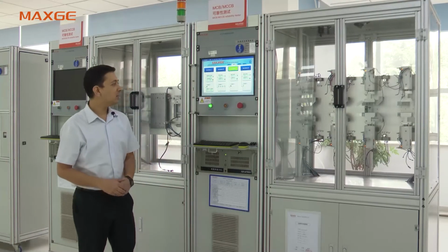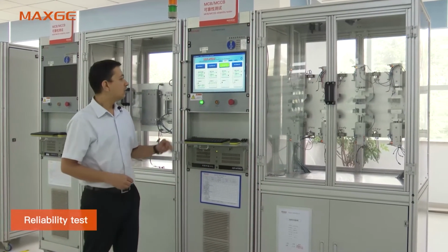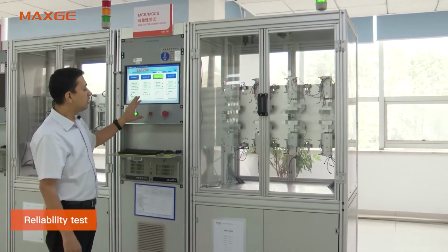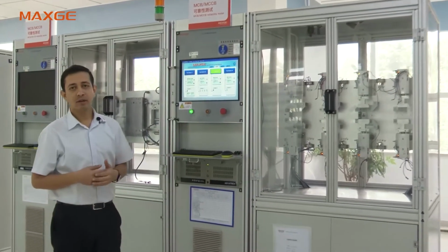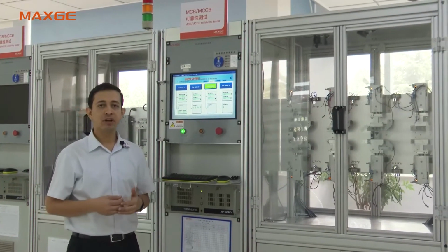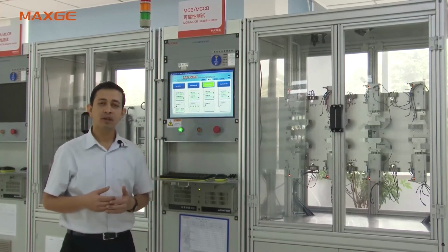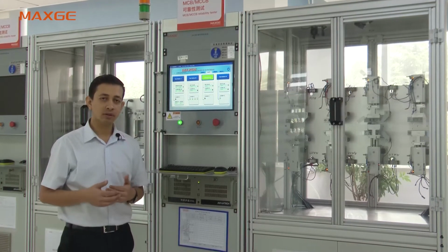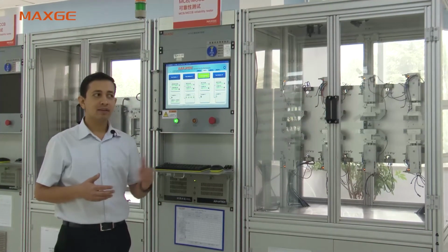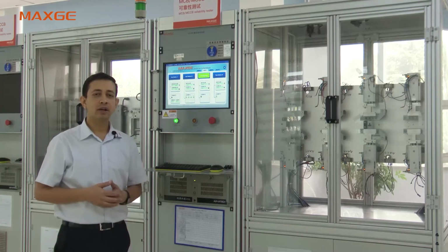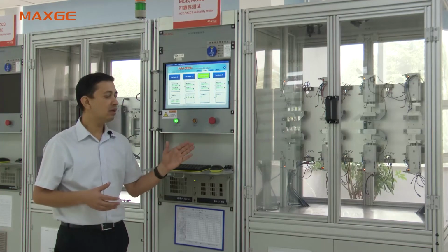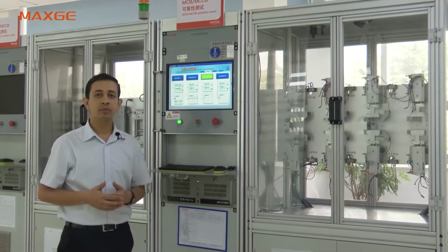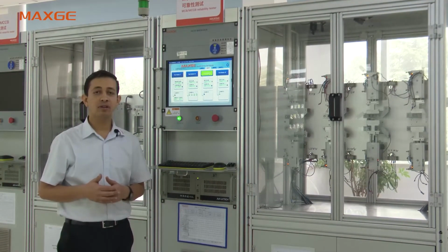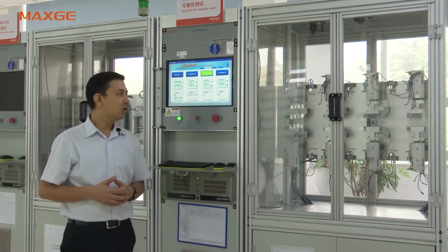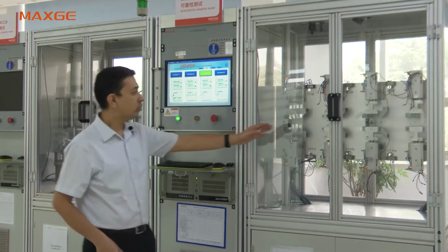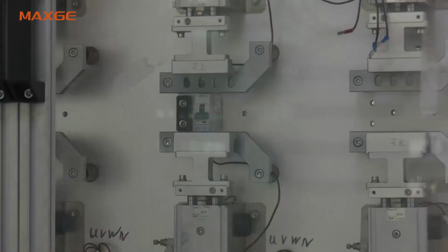Now we are standing at the mechanical endurance tester. During this test, no current is applied, only continuity is checked, and the MCB or MCCB is tested for several operations. As I told you earlier at the electrical endurance testing machine, our MCB qualifies for 20,000 mechanical operations and our MCCB qualifies around 10,000 mechanical operations. Here the test is already running, you can see.